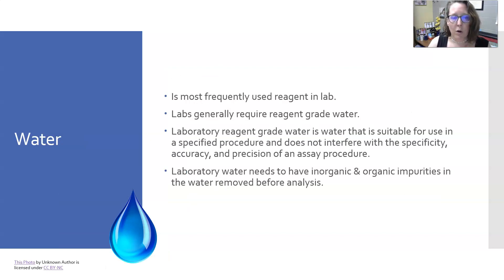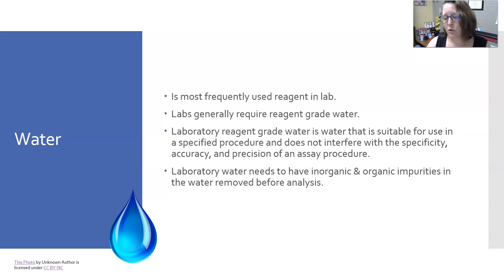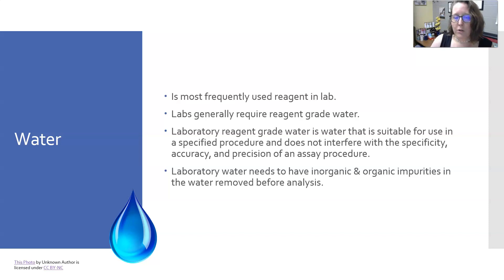Let's talk about water. Water is the most frequently used reagent in the lab. Labs generally require reagent grade water — water that is suitable for use in a specified procedure and will not interfere with the specificity, accuracy, or precision of the assay procedure. For example, if you were trying to analyze trace metals in a sample, you would not want to use tap water because it may have lead from lead pipes in it. Lab water needs to have inorganic and organic impurities removed before analysis.